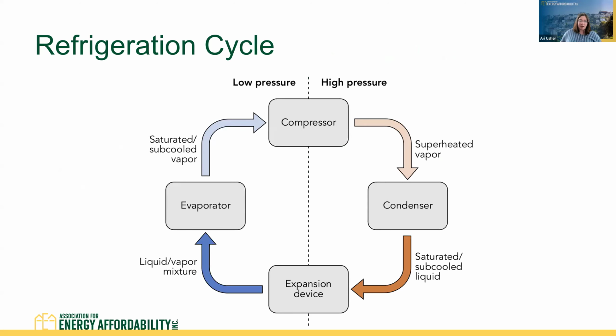So how do heat pumps work? Just really quickly, the refrigeration cycle: on the low pressure side, heat is absorbed into the refrigerant. And then on the high pressure side, that heat is released from the refrigerant. So this can be reversed for heating or cooling. For the water heating application, we've got heat being absorbed from the ambient air and being released into the water.